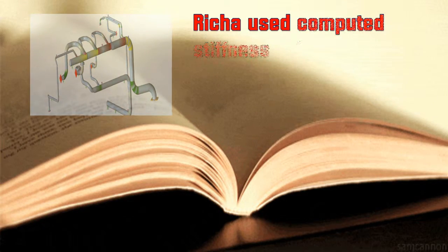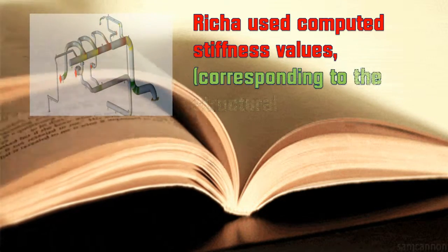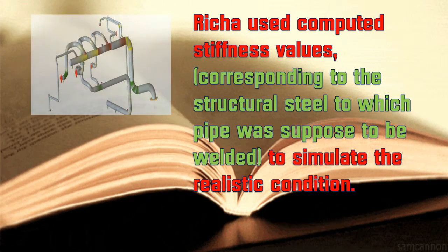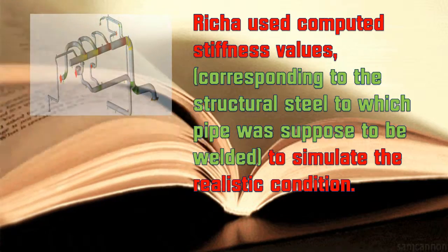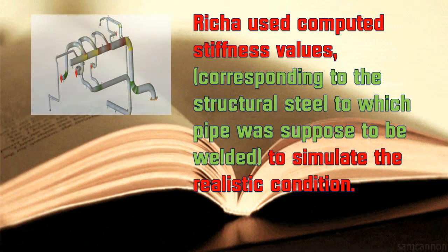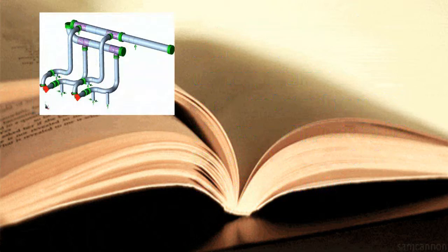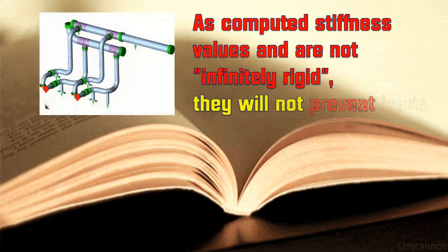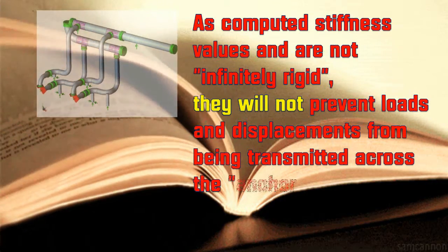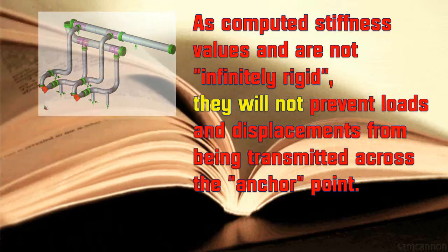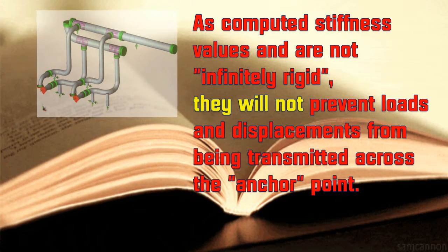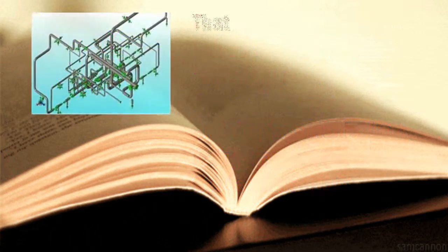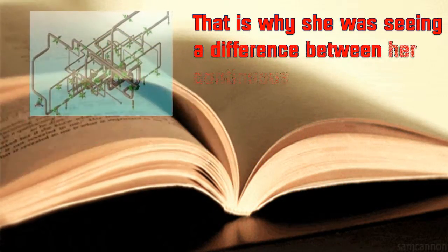Richa used computed stiffness values corresponding to the structural steel to which the pipe was supposed to be welded, to simulate the realistic condition. As computed stiffness values are not infinitely rigid, they do not prevent loads and displacements from being transmitted across the anchor point. That is why she was seeing a difference between her continuous and partial models.